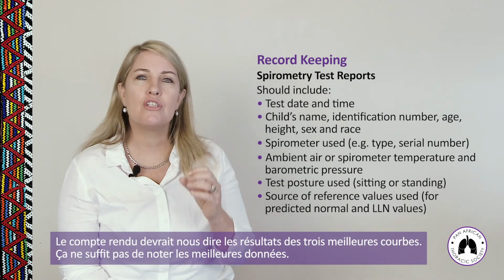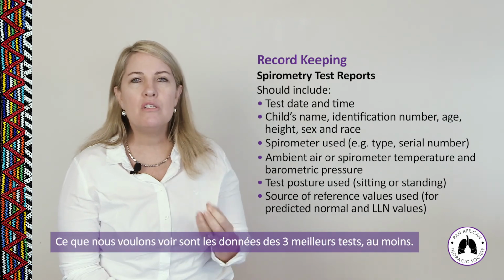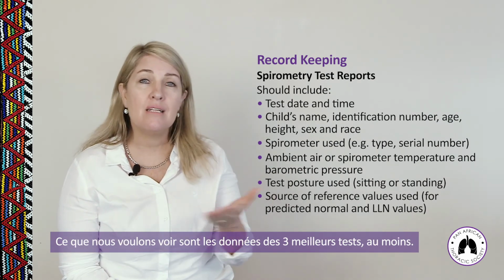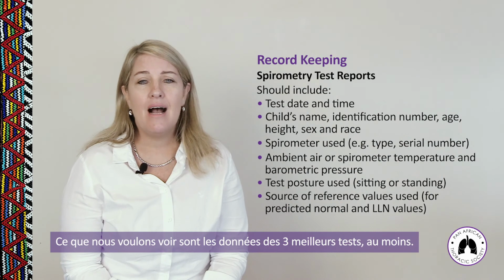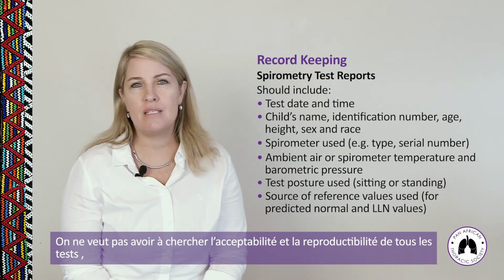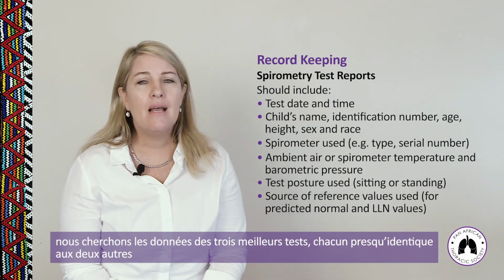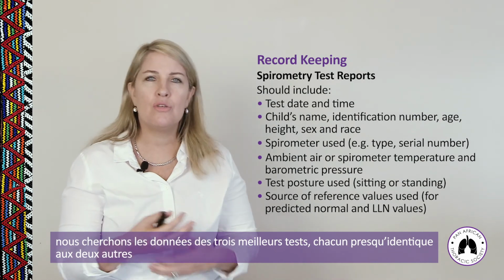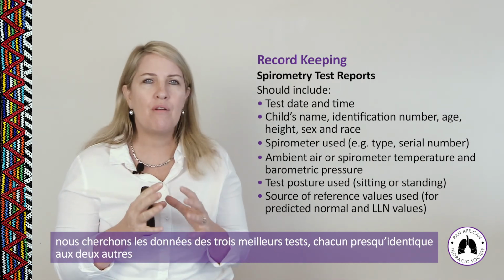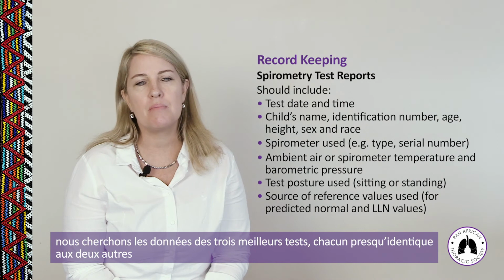It's not good enough to just see the best data. We want to see data from at least the best three tests done, so that we can look at every test for acceptability and repeatability, and compare the measurements to one another. We want three almost perfectly identical spirometry measurements.